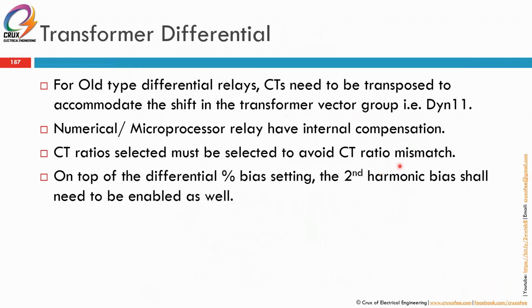Okay. So for all old type differential relays, CTs need to be transposed to accommodate the shift in the transformer vector group: DYN11, DYN5, DYN1. So you have to change the CT connection, you have to transpose it, because you need to compensate for the vector group that has changed. But for the new numerical microprocessor relay, there is no issue, because there is an internal compensation within that relay.